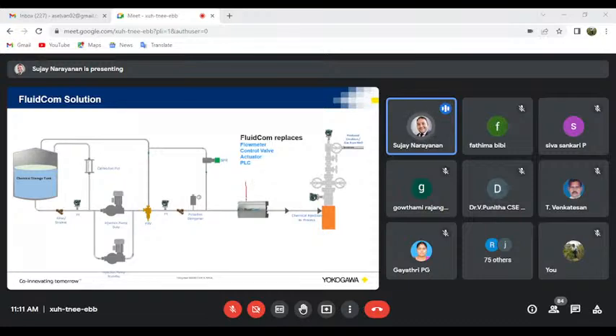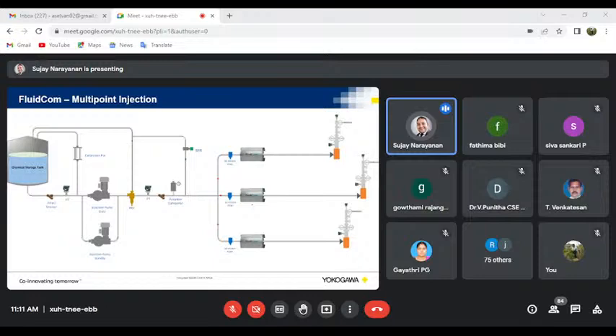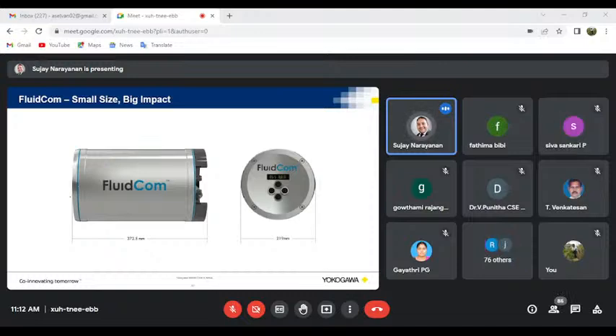You just need to give a set point to the FluidCom, say 2 liters per hour, and then it's going to control your discharge to 2 liters per hour. Then you have 3 FluidComs over here, one on each line, so it can individually control the flow rate. For example, if you need 3 liters for injection point 1, 2 liters for point 2, and 0.5 liters for injection point 3, it can individually control the injection rates, and all you need is one pump. It's a compact device, a little more than a foot long, and 220 mm in diameter.